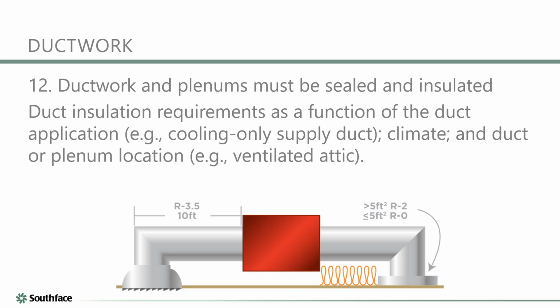Duct insulation is really important. We talk a lot about this in residential, but really it's about condensation. You never want to have the warm, moist air touching that cold surface on the ductwork and making that condensation. So really important. We see this a lot. We get a lot of complaints of why are my ducts spitting out water and things like that. So you really have to see that insulation there, and they need to be sealed as well. So generally, what are we sealing that with, Burke? I mean, typically they're sealed with tape or mastic.